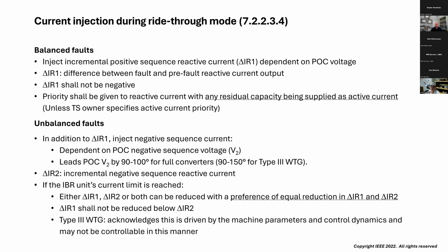So it's kind of separated here into either balanced or unbalanced faults. For balanced faults, the idea is that the IBR unit needs to inject an incremental reactive current in the positive sequence based on the POC voltage. And the incremental positive sequence reactive current is just going to be the difference between the reactive current during the fault and the pre-fault reactive current output.